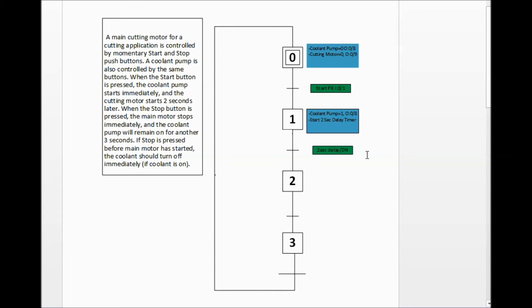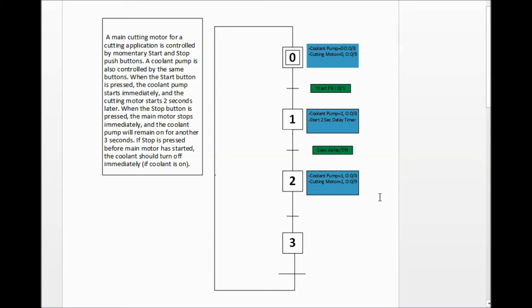Once the timer is done we move to step 2. At step 2, the cutting motor comes on and the coolant pump remains on. Coolant pump is set to 1 at O:0/8, and cutting motor is set to 1 at O:0/9. Step 2 continues until the next transition. That transition is when the operator presses the stop button. The stop push button is wired normally closed, so we look for NOT stop PB — a low signal — to move to step 3.